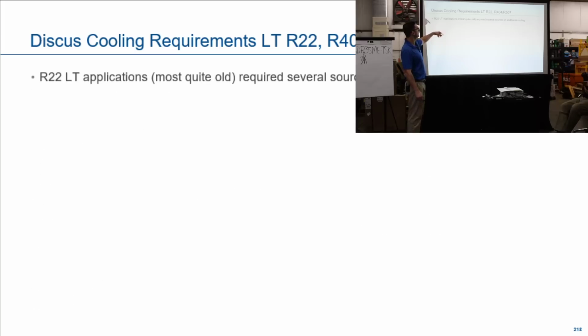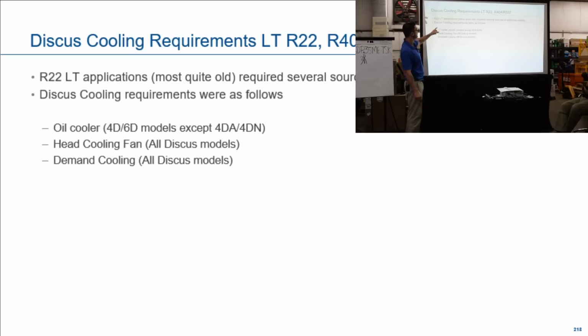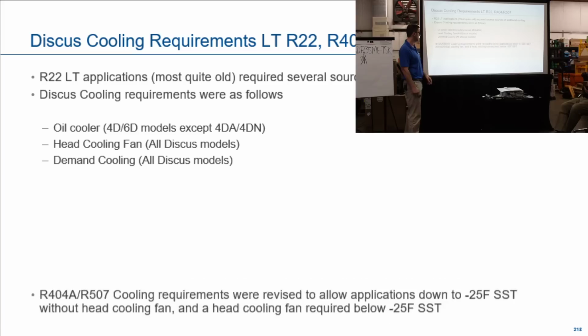So, R22 low temp applications require several sources of additional cooling. Discus cooling, like you used to have oil coolers. One of the compressors that we're going to tear apart has an oil cooler on it. We don't sell oil cooler models anymore. Okay, head cooling fan or demand cooling.